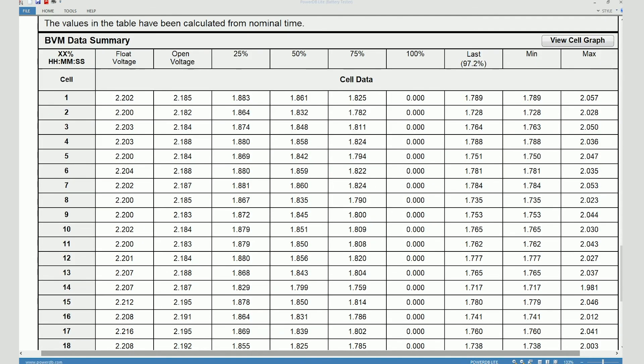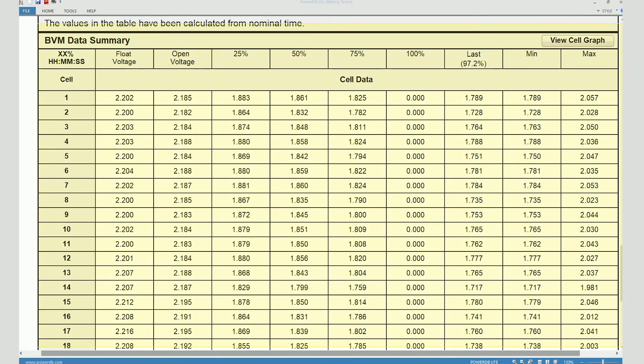The BVM data summary is similar as well. You can see for all the cells, you can see the float voltage value, the open voltage value, and the voltage values recorded at different stages of the discharge test. And finally, you can see the minimum value and the maximum value logged by the BVMs on each of those cells.